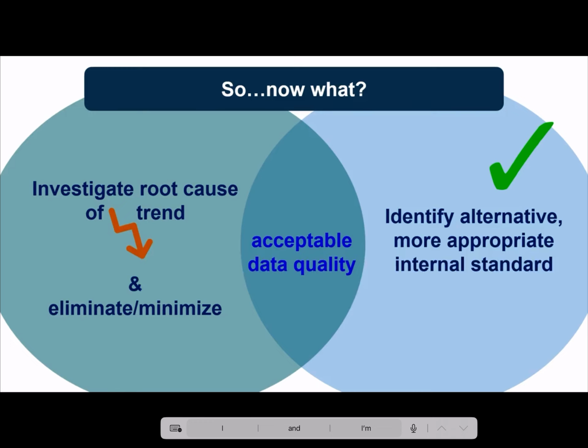So now what? The big thing that came out of this was that the internal standard was not on the radar until we looked into the data, looked at the response factors, and did a bit of plotting and trending. Immediately, based on some additional advice, an alternative internal standard was identified and purchased. There were also some additional things to look at, essentially the downward trend of arsenic, because unfortunately we can't eliminate that from the method. That's a required analyte, so there were some additional steps taken to figure out exactly what was going on there.